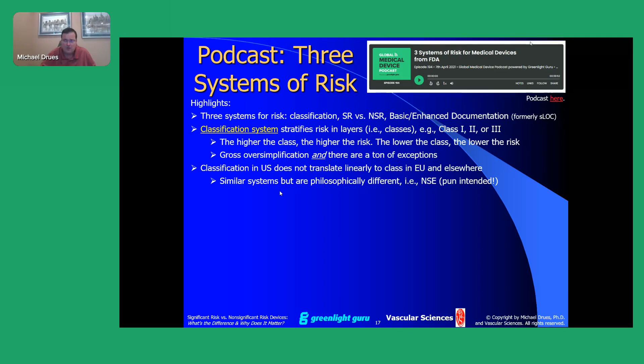Of course, the topic of today's webinar, which we're going to be digging into more and more as we continue, is the SR versus NSR system. As we'll discuss, this is very important in clinical trials because it will help determine if your device is going to require what we call an investigational device exemption or an IDE, or is it what we call IDE exempt? And the determination, might be a bit of a surprise to some of you, determination of the significant versus non-significant risk status is not made by the FDA. It is not made by the IRB, or the IRB has to agree with you, but the determination is not made by them. It's made by you. It's made by the medical device company.